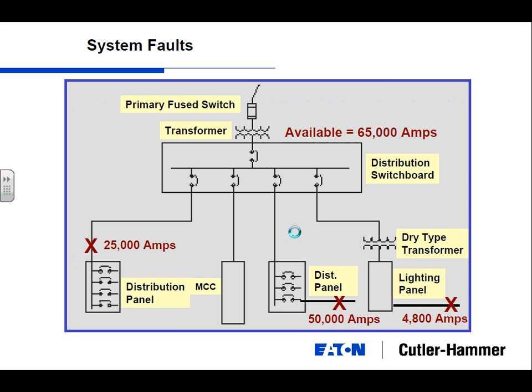It's the dry type transformer. Anytime you put a dry type transformer in your distribution system, you basically set a new maximum available fault current on the secondary side of it. The transformer itself has mechanical limitations on how much energy is going to couple from the primary to the secondary of that transformer. When I say couple, think about a transformer. You've got the primary voltage. It's magnetic, so you're wrapping it around an iron core, and you've got the secondary, which is magnetics, picking up the other side of the field.